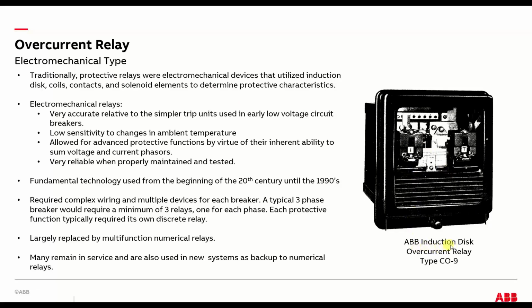This here is your overcurrent relay, electromechanical type. This is an ABB CO9. This goes back many years. It was probably in production for maybe 80 years, this thing. This started out as a Westinghouse product, and then when ABB acquired it, it became ABB. So you might see some old equipment with the Westinghouse nameplate or the ABB nameplate. It's the same relay. We own it, and contact us for information that you need on it.